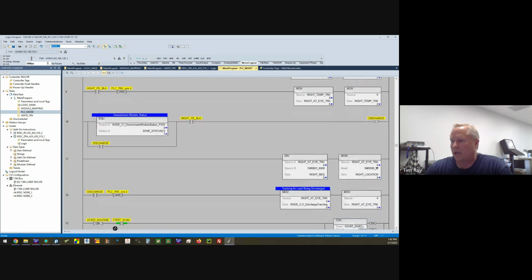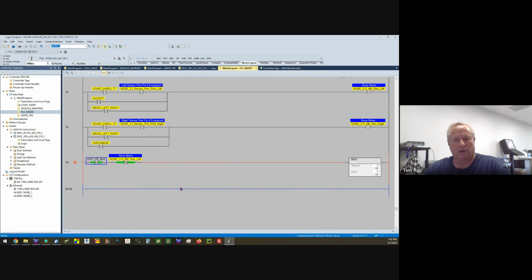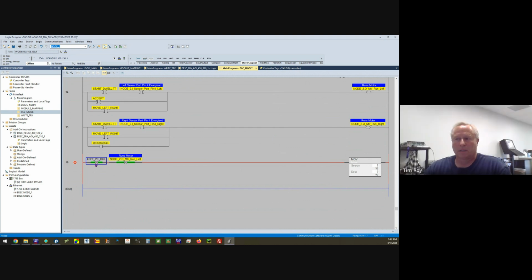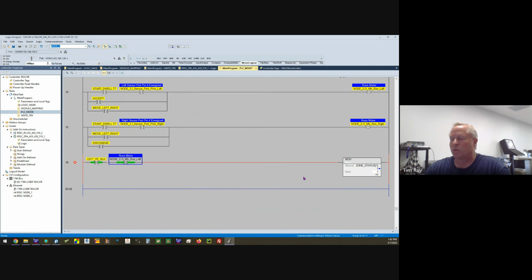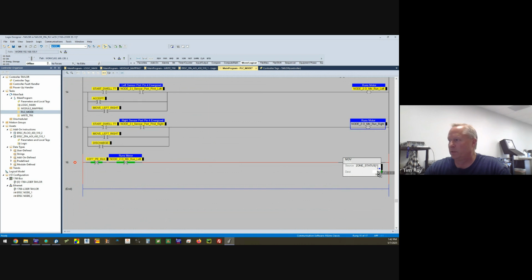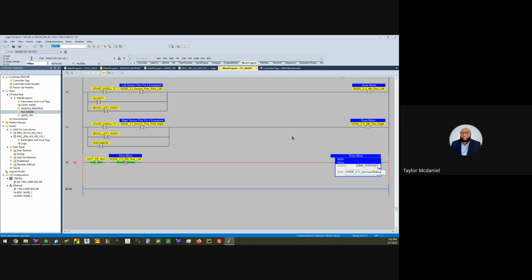Left photo eye. We're going to act just like a card. If the sensor's not blocked and the motor's not running, what zone status is stopped and not blocked? Status 1, empty. Where are we going to move it to? Output, upstream status. Got it.